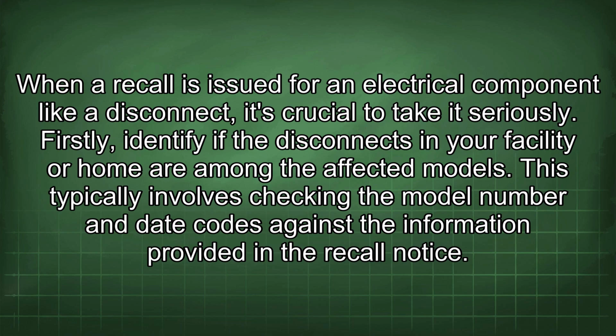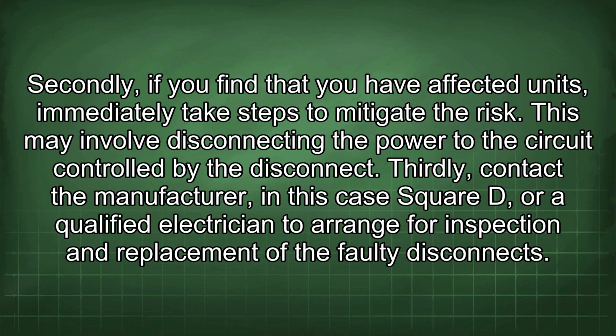When a recall is issued for an electrical component like a disconnect, it's crucial to take it seriously. Firstly, identify if the disconnects in your facility or home are among the affected models. This typically involves checking the model number and date codes against the information provided in the recall notice. Secondly, if you find that you have affected units, immediately take steps to mitigate the risk. This may involve disconnecting the power to the circuit controlled by the disconnect.